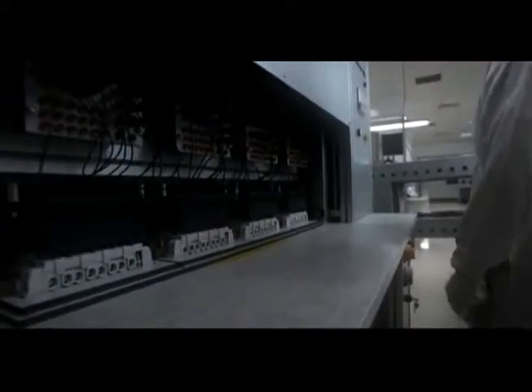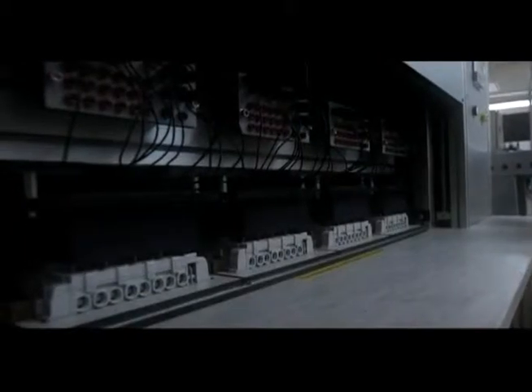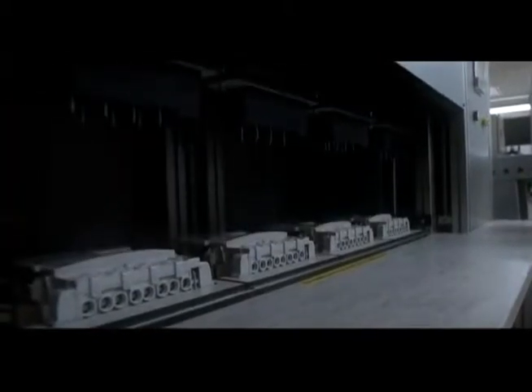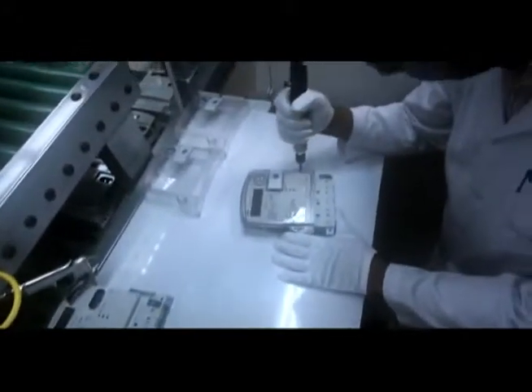We use high voltage testing for isolation testing, and this high voltage machine sends a large amount of electrical current directly on the meter terminal block. The meter cover is then added and permanently closed using pressure in either a single phase or screws in a three-phase meter.